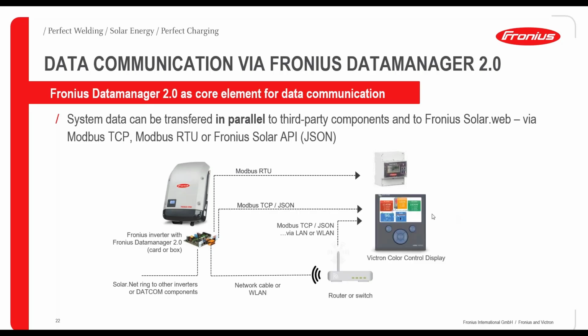From Victron side, important is we have got this - it sends out the protocols, the Modbus TCP and JSON protocols, which can be directly linked to, for example, the Victron Color Control GX or via a network. It means this is very, very important to transfer in parallel to third-party components, in this case the Victron Color Control, the data, so that you have this, for example, on-site monitoring, and you receive lifetime data and all the log data from our inverters, and you have it in the Victron device.